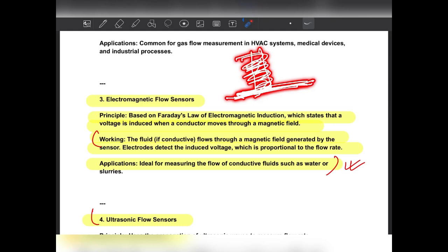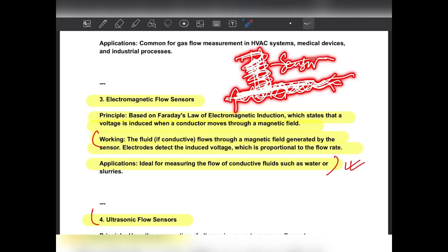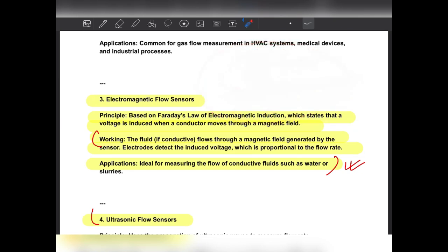There is a coil wound in the sensor, and when you place this in sea water and the water is continuously flowing, there is a magnetic field change, because current is going through this sensor and it creates a magnetic field. When the speed of the water is continuously changing, this magnetic field will change, and the change in magnetic field basically tells us about the speed of the ship. So the main purpose of the electromagnetic flow sensor I already explained. The flow passes through a magnetic field generated by the sensor. Electrodes detect the induced voltage, which is proportional to the flow rate. Okay, so we are calculating speed also.